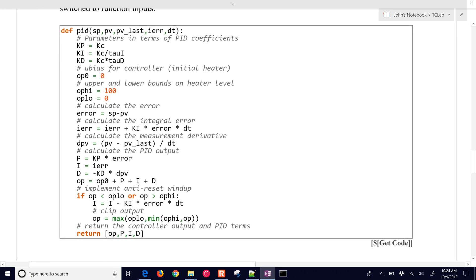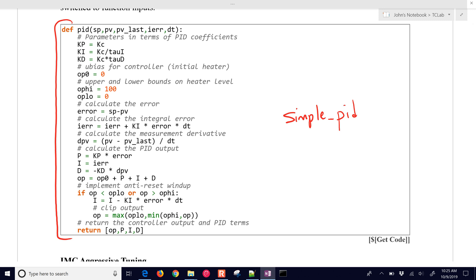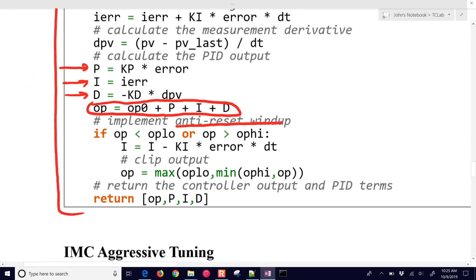We have a PID function that you can use, which helps you reuse code so you don't have to program the PID controller each time. There are also other packages in Python, like simple-PID, that you can pip-install and use. In this function we have the proportional, integral, and derivative terms, and the output is the addition of those together. We also implement anti-reset windup, so that if we're outside the output low or output high limit, it doesn't continue to increment the integral term.